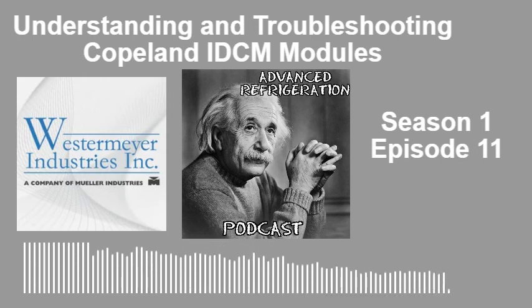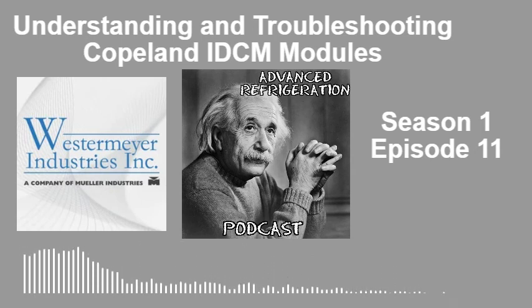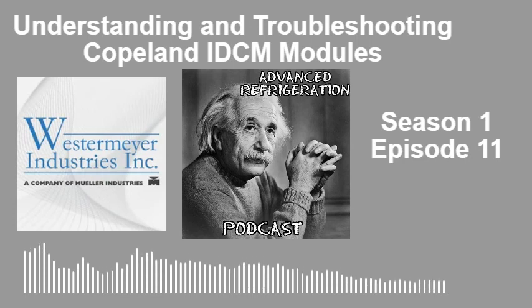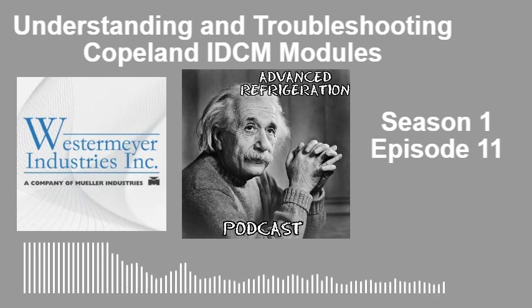Some, I know this was talked about online the other day, some manufacturers use all three lines. You should run all three phases through there. But if you only have one phase running through, it has to go through the C terminal, and it works fine. I mean, we've got over 150 protocols that are wired that way, where Hussmann only took the one wire through the C. So that'll work fine.